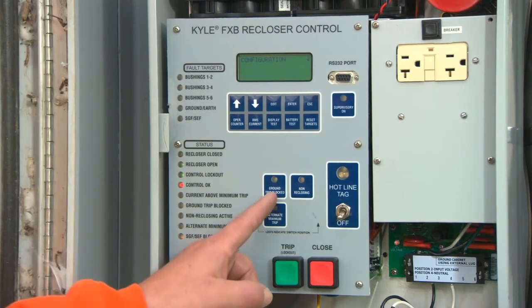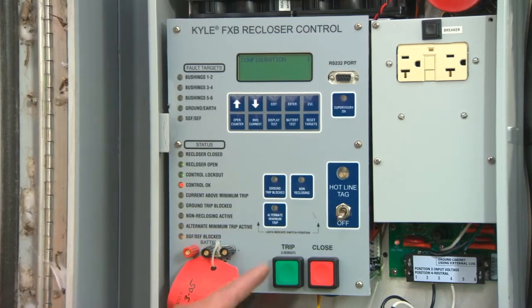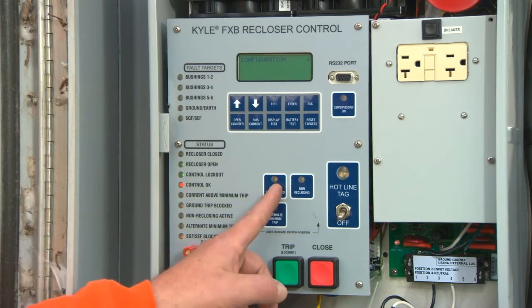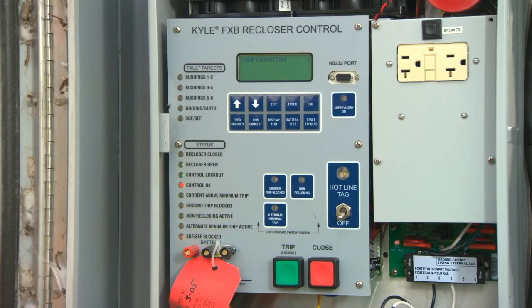Next, let's take a look at the ground trip blocked button. If you are performing switching procedures or taking this recloser in and out of service, it is recommended that you push the ground trip blocked button. To turn this off and to make the ground setting active again, press the button one time.